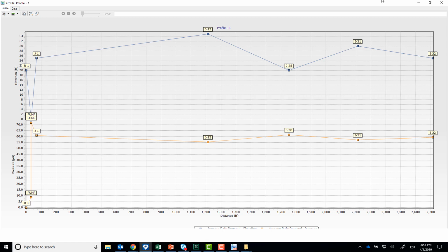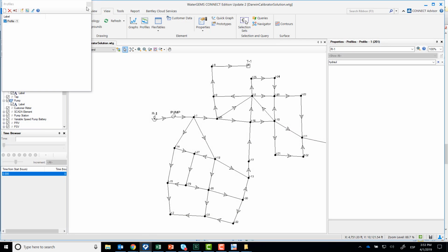So that is the reason that we always recommend you think of your system in terms of hydraulic grade line, right? Even like when you think of pressure zones, it's like, okay, between this grade line and this, 150 and 140, and then I have a PRV, and then that brings it down between like 110 and 90 or whatever. So we just kind of think of our systems as a progression where the head losses get shown in that downward slope. Okay, going back to our exercise.